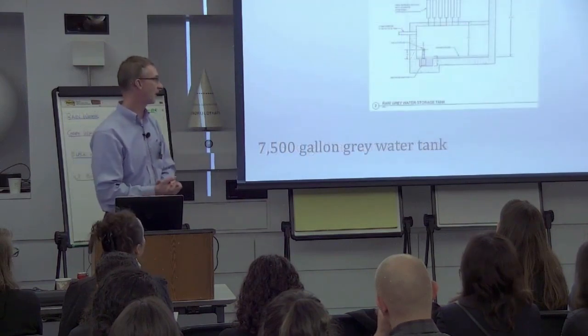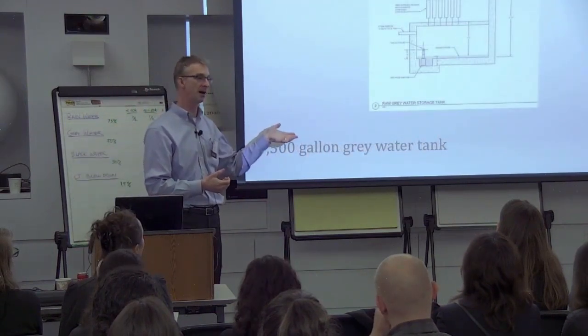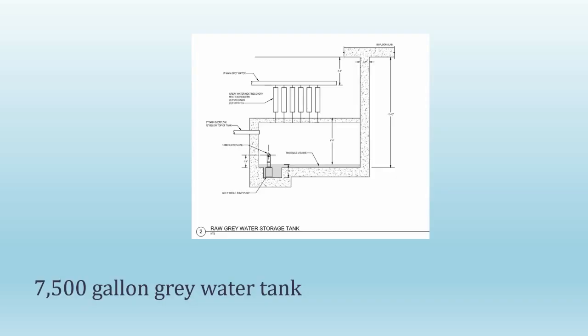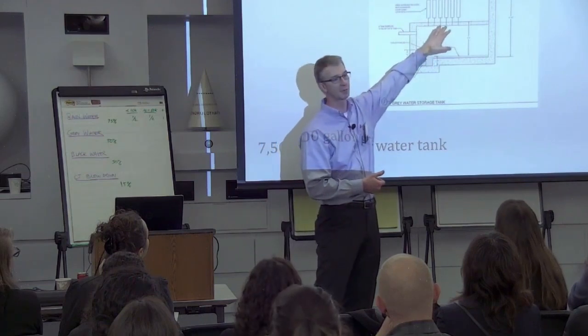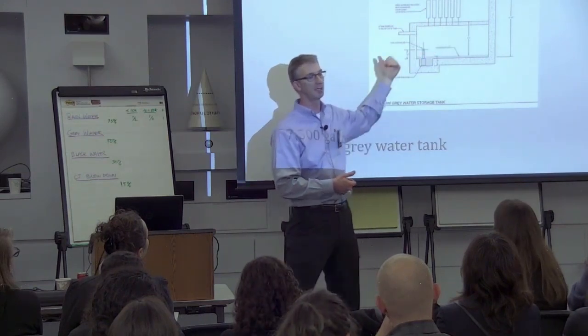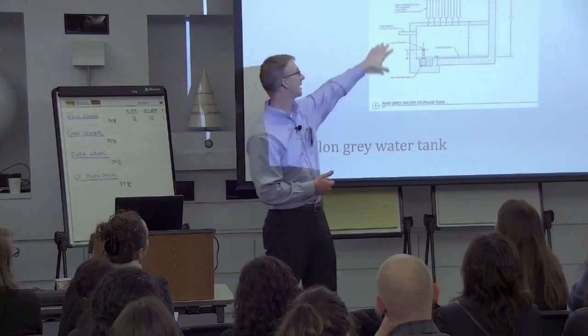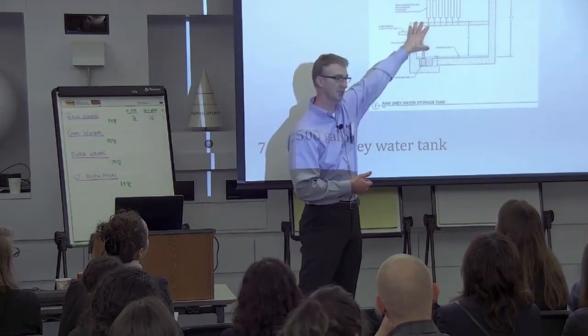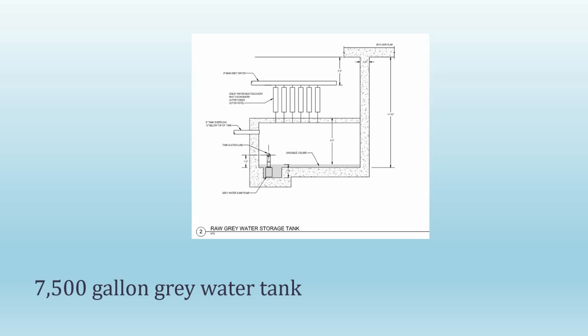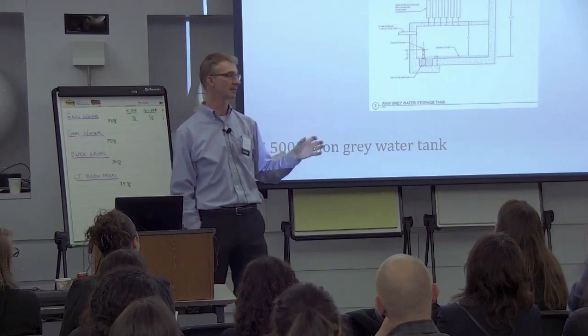And then for gray water, what we went with is a 7,500 gallon gray water storage tank. It's a little oddly designed because we're collecting only the showers in the building. Because we have hot shower wastewater, we are going to capture the waste heat from the showers and preheat the domestic hot water. So we have this unusual tank with the heat exchanger above, and the gray water storage tank below. We could probably go smaller with this tank size, but we wanted some buffer capacity in case anything happens to the system.